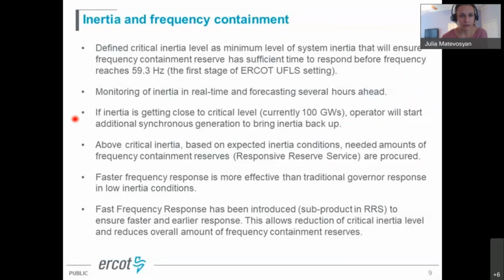So, all in all, going to inertia and frequency containment concerns, we thought there may be a concern, so we defined early on a critical inertia level, which is the minimum level of inertia that will ensure frequency containment reserve has sufficient time to respond, so we don't touch the first step of under-frequency load shed. We since monitor inertia in real time and forecast it several hours ahead. If inertia gets close to the critical inertia level, which is currently 100 gigawatt seconds, the operator can start additional synchronous generation and bring inertia back up.